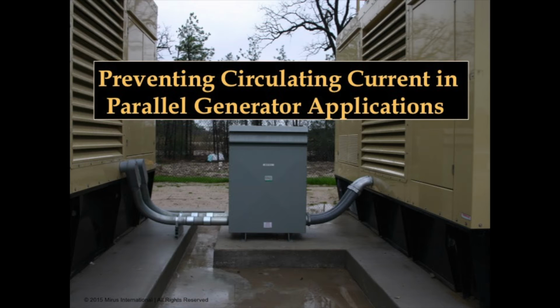We have developed a very effective solution for the problem, although, as you'll learn during this presentation, it is more a voltage matching issue than a harmonic distortion one. Anyone who has been involved in paralleling 2 or more generators will know that concern needs to be given to the possibility of circulating current in the common neutral. Or when the neutrals are not bonded together, current in the neutral to ground connections. These can be particularly heavy when the generators being paralleled are of different pitches. Preventing this has proven to be very difficult. But now there is an easily applied and very effective solution.